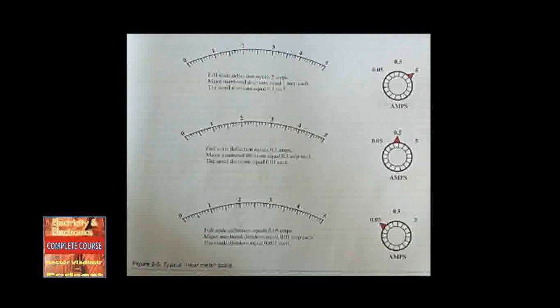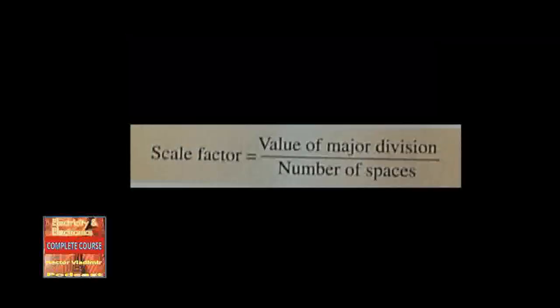The second example has a full scale deflection equal to 0.5 amperes; the major scale markings are equal to 0.1 amp each, and since there are 10 spaces between each major division, each small mark equals 0.01 amperes, or 10 milliamps. In the third example, the range selector is set to 0.05 amps, making full scale deflection equal to 0.05 amperes. Each major division equals 0.01 amperes, and each small mark equals 0.001 amperes, or 1 milliamp.